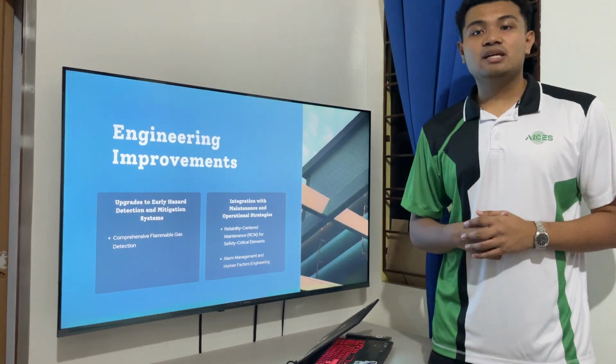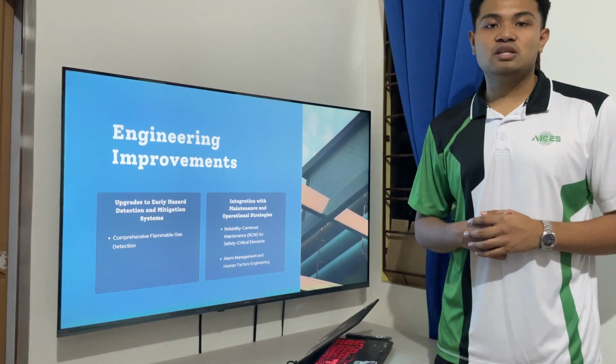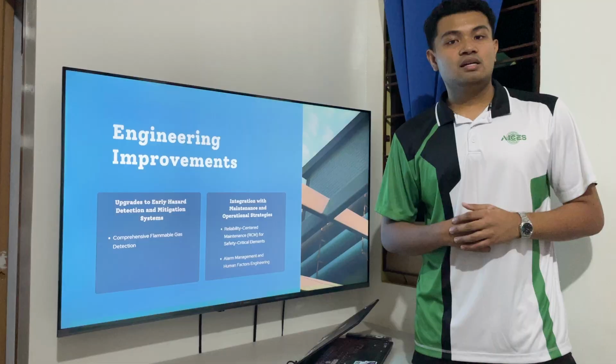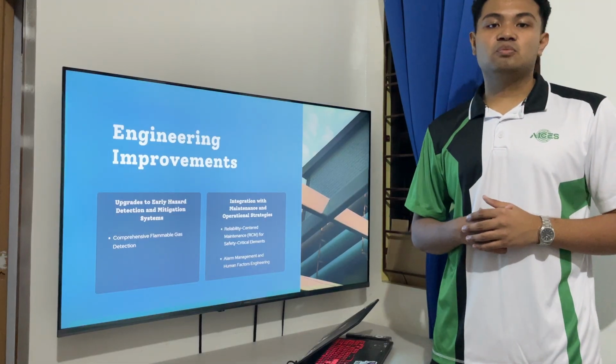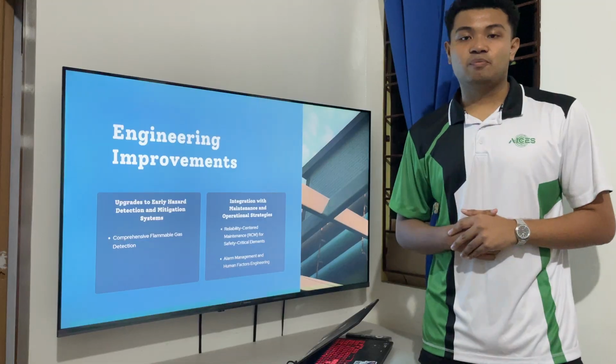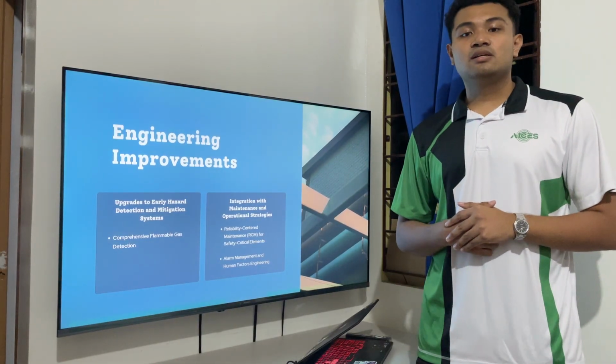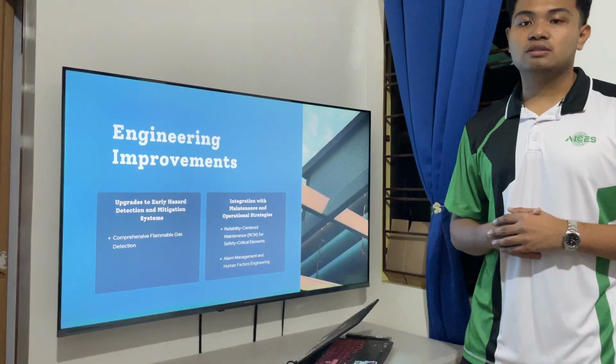Furthermore, a comprehensive alarm system rationalization and management review based on international standards is essential to address the control room alarm flooding that masked the critical overfill at Buncefield, ensuring that critical conditions are presented clearly to support effective operator decision-making.